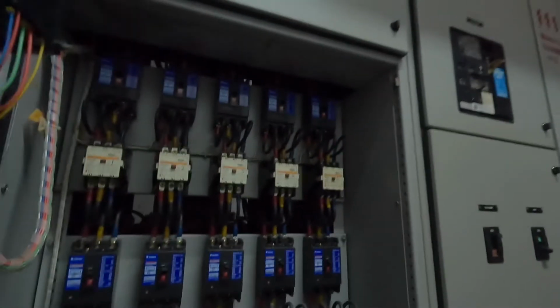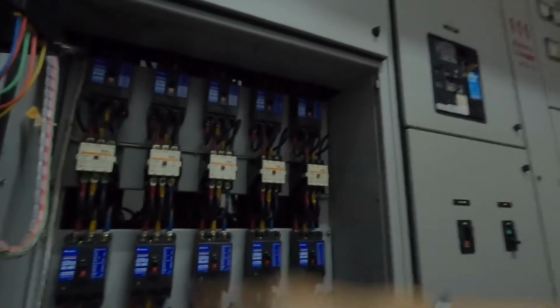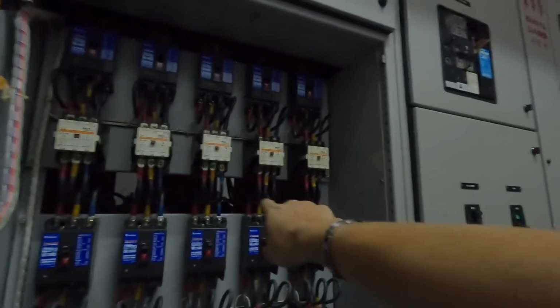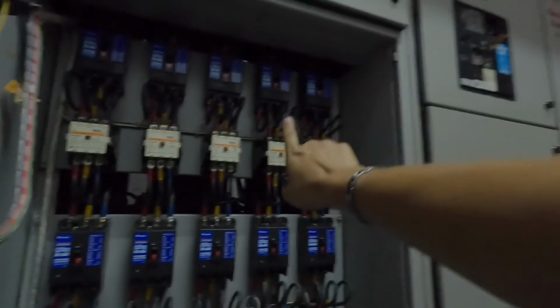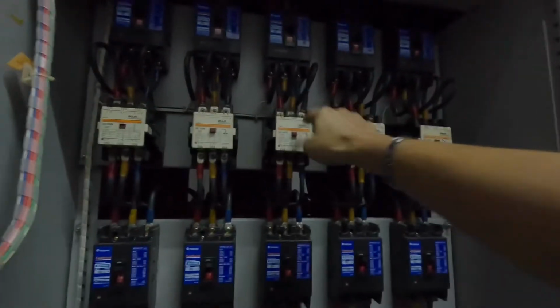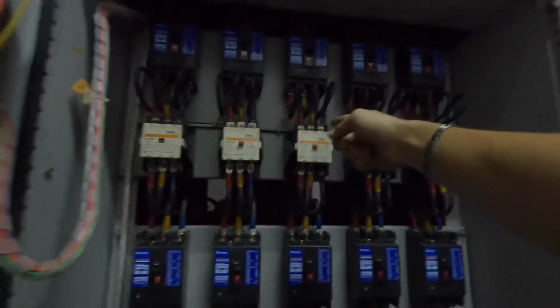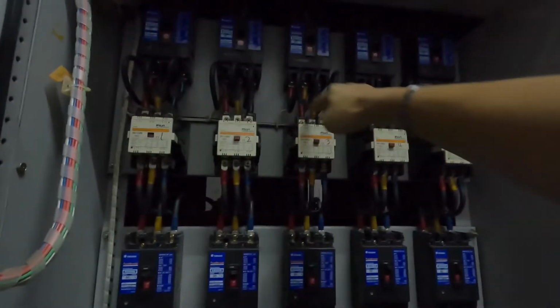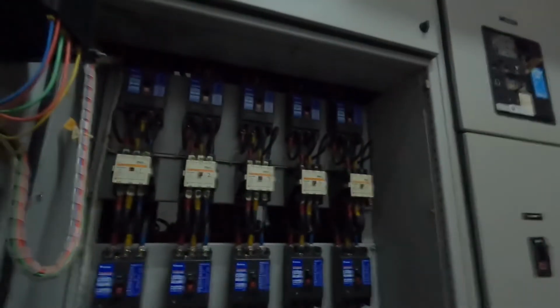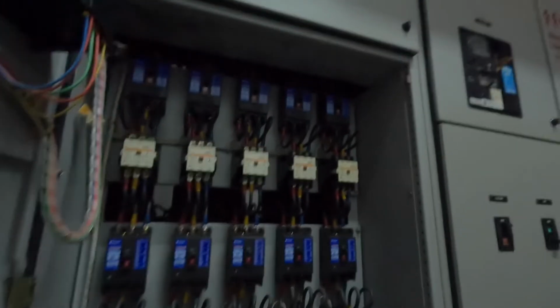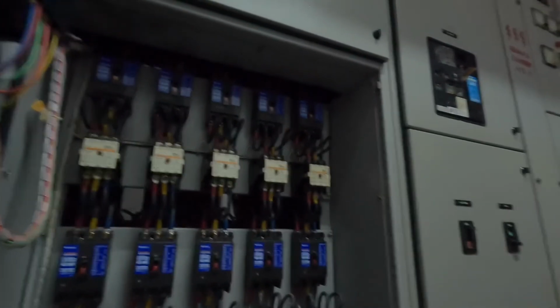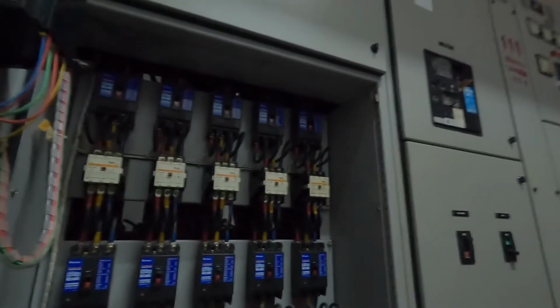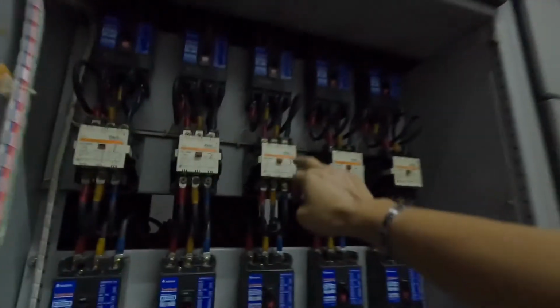But if your contactor is jammed, then suddenly no power from TNB, but your motor is still turning or your cap bank is not discharged yet, there's output kVAR here. Suddenly your TNB supply comes back, then it will clash and your incoming side will have an explosion. It will cause your termination to explode and cause your breaker or your ACB or your contact to be damaged. So the cost is very high to repair. So the contactor is actually a protection, we call it no volt release.